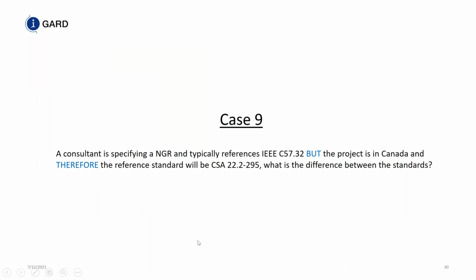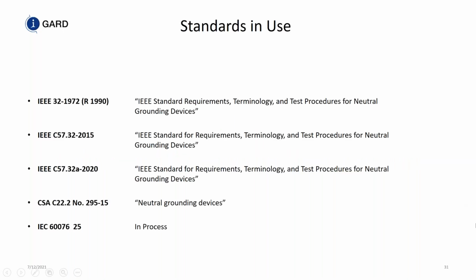Case number 9: a consultant is specifying a neutral grounding resistor and typically references IEEE C57.32, but the project is in Canada and therefore the reference will be CSA C22.2 number 295. What are the differences between the standards? If we look at all the standards that relate to neutral grounding resistors, we have IEEE 32, which has been around for a very long time, since 1972, reaffirmed in 1990. It's basically standard requirements, terminology, and test procedures for neutral grounding devices.